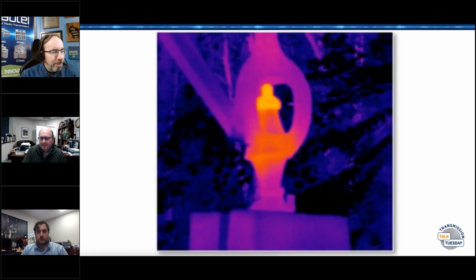You were talking about stress earlier, mechanical stress, and this is an example. That's an old push-pull base insulator, from something that used to be called KQV in Pittsburgh. Nothing else was anywhere near it. The array was energized, and I'm looking at this with a thermal camera saying, why is that insulator hot? It was just thermal stress in that particular leg, the base was tilted in a funny way and getting a lot of pressure.